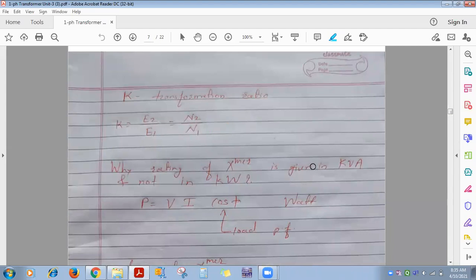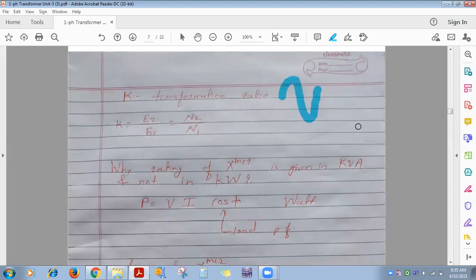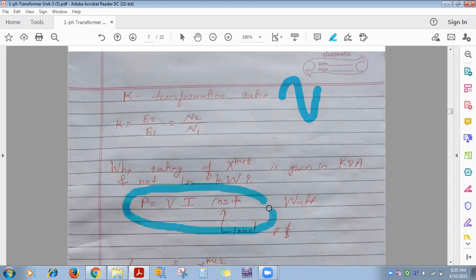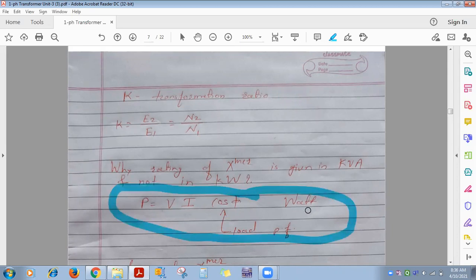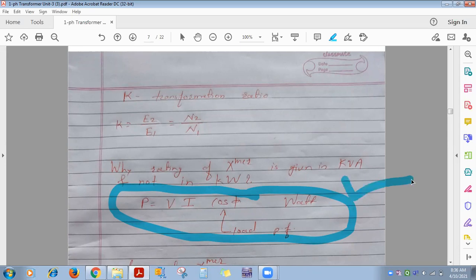Another reason: core loss (iron loss) depends on voltage, and copper loss depends on current. Since losses involve both voltage and current independently, the rating is given in volt-amperes (KVA) — not kilowatt. For example, a 1 KVA, 110V/220V transformer has a nameplate with KVA rating, V1, and V2. From these: I1_full_load = KVA × 10³ / V1, and I2_full_load = KVA × 10³ / V2. For 1 KVA, 110/220V: I1_FL = 1000/110 = 9.09 A, and I2_FL = 1000/220 = 4.545 A.